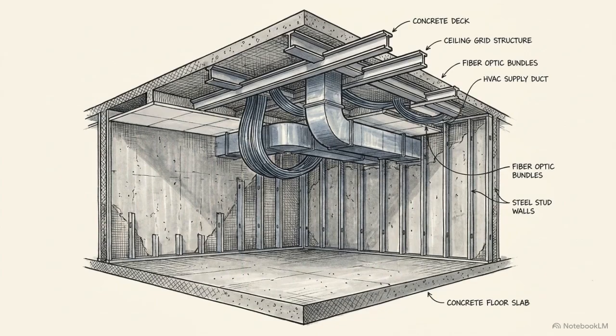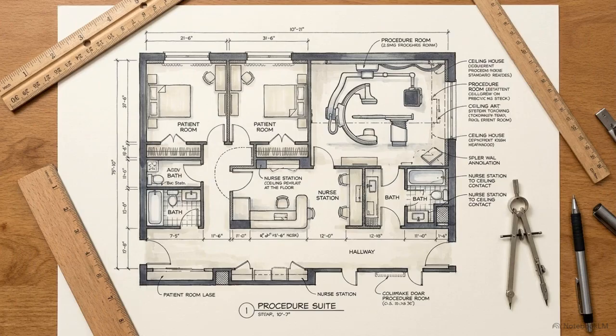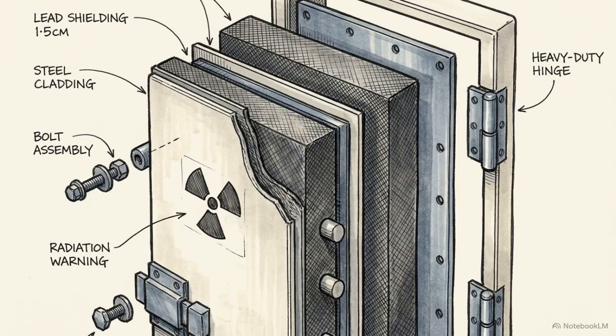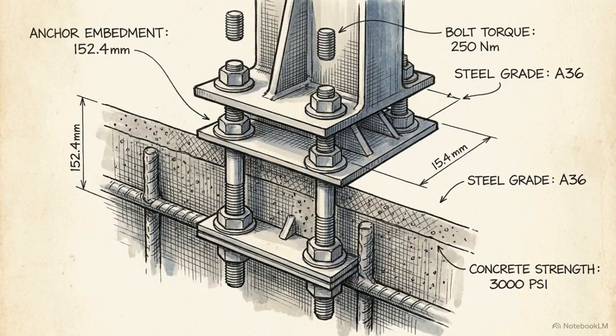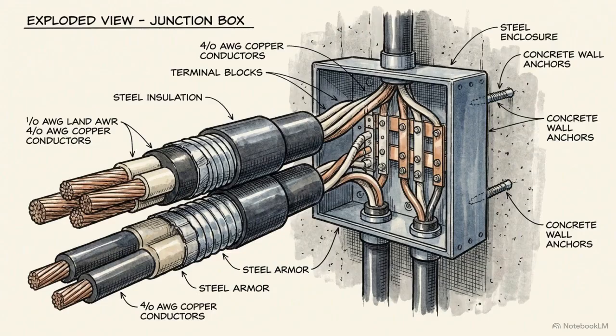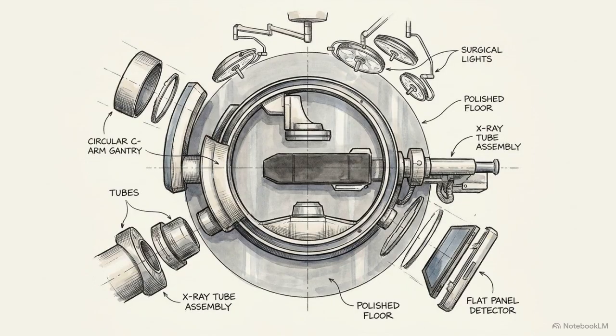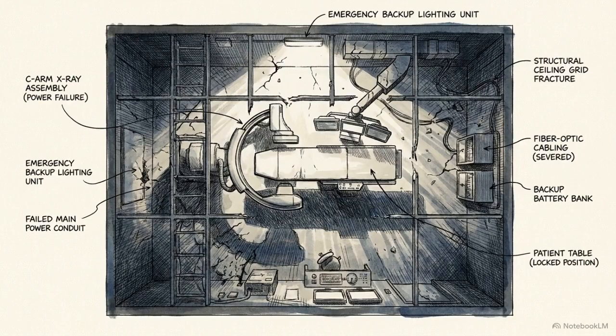Installation is not a simple equipment drop. It requires a specialized build-out that transforms the hospital room into a cohesive, life-saving machine. The engineering must balance extreme competing physical constraints. It must contain massive radiation output, limit vibrations to sub-millimeter tolerances, and support immense transient power draws. The procedure room itself operates as an integrated, life-saving machine. A failure in the surrounding physical infrastructure equates directly to a failure in the clinical intervention.